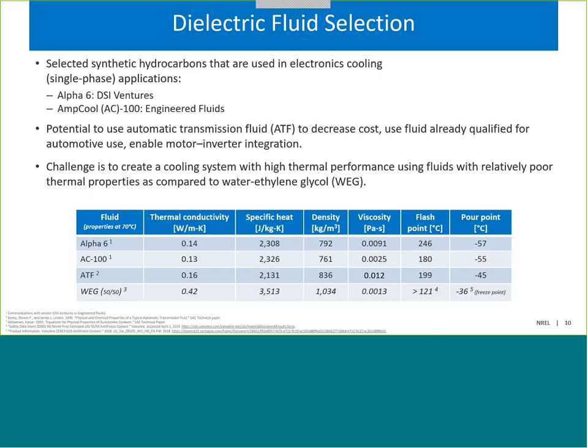The table below compares the properties of the two dielectrics with that of ATF. I'm also showing the properties of water ethylene glycol, or WEG, for comparison. As you can see, the two dielectrics have properties that are very similar to ATF. They have slightly lower viscosity, and that's a good thing. The downside of these dielectrics is their poor properties as compared to water ethylene glycol. For example, water ethylene glycol has a thermal conductivity that's about 3 times higher than that of the dielectric fluids. Also, the dielectric fluids have higher viscosities, which can result in higher pumping power. So one of the challenges here was to create a cooling system with high thermal performance using fluids with relatively poor thermal properties as compared to WEG, which is the conventional coolant in automotive electronics.